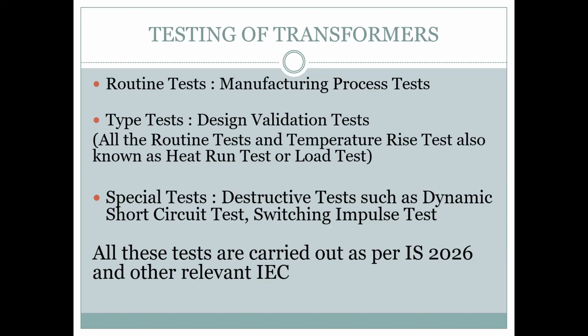So this is the destructive short circuit test. If you survive, you survive. Once you contact, that will spoil the transformer. Normally it is like that. Ideally, if you order 10 transformers, one will be tested, and it has to be used on reduced load afterwards. It is like you have suffered a heart attack: the doctor will give you a lot of do's and don'ts, like don't go for a marathon run. That is taken care of in the pricing. Yes, pricing, that is the commercial part. But another less important thing here: it has already suffered one heart attack.